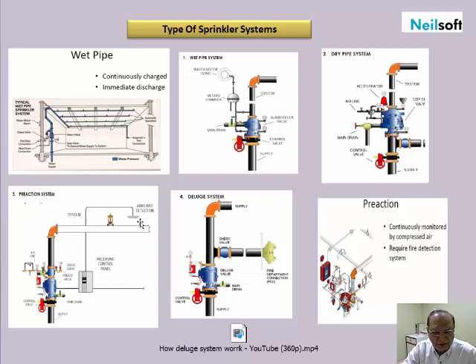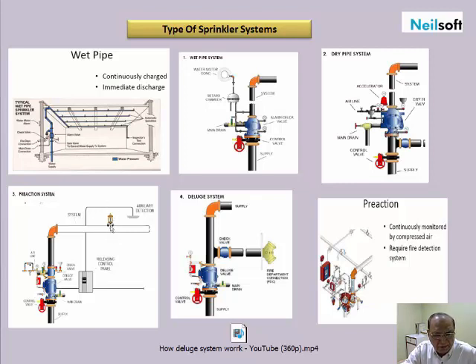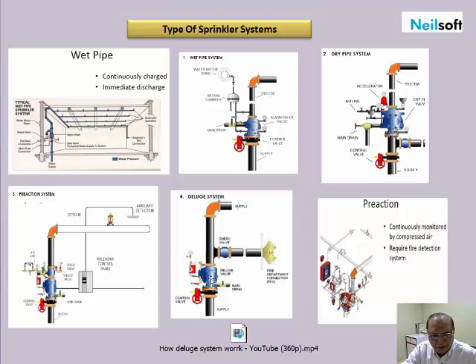The pre-action system will take the signal from auxiliary detection systems that locate fire, smoke, or heat. Because, as you can see, the glass bulb type sprinklers will discharge water only when the rated temperature is reached. In the deluge system, the system is charged up to the valve and there is no water beyond it — the sprinklers or nozzles are installed as open nozzles, so only after opening the valve will water flow.